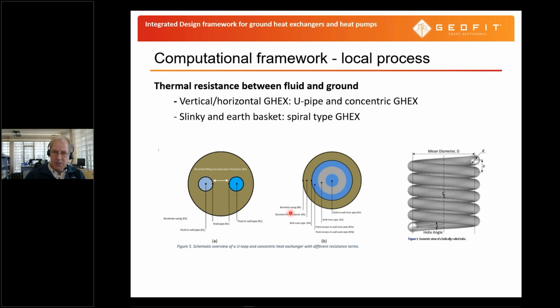Then the next step is to take a look at the thermal resistance between the fluid and the ground. For a vertical borehole, we have a typical U-pipe configuration. This is a top view. Here we have the borehole radius with the borehole filling. Here we have 2 pipes, one going down and one going up.